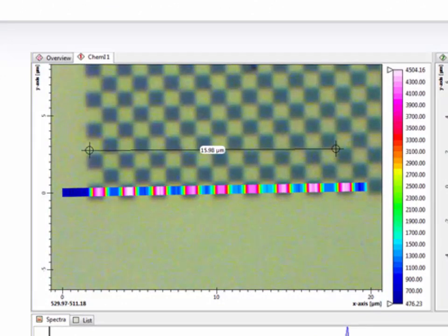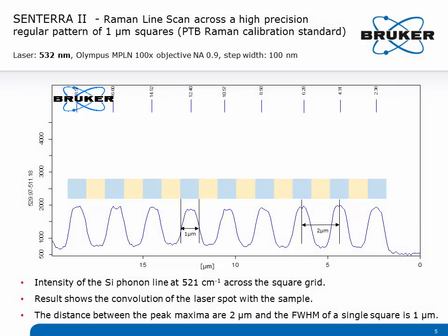In this image, you can see a line map recorded along one end of the chess grid. A bright color means high intensity of the phonon band and a dark color means low intensity of the phonon band. In this overlay of the chemical information over the visual image, we already have a good indication that the square is well resolved. The intensity of the phonon band along the chess grid line has been extracted and is shown here. The distance between two peaks is exactly 2 µm and the full width at half maximum of one peak is 1 µm, which equals exactly one square.